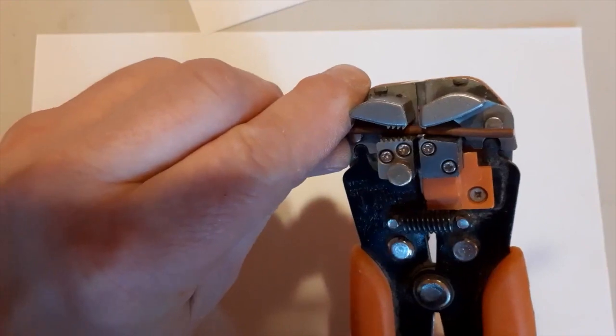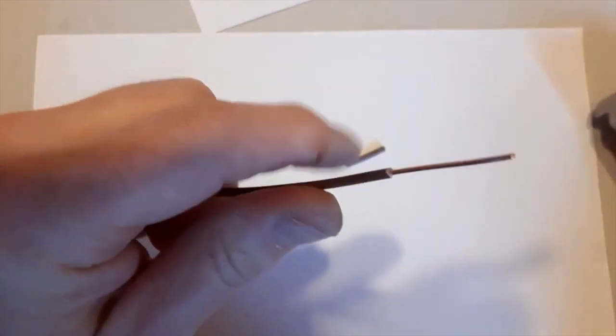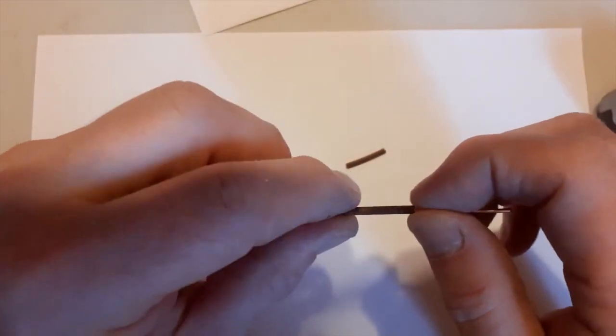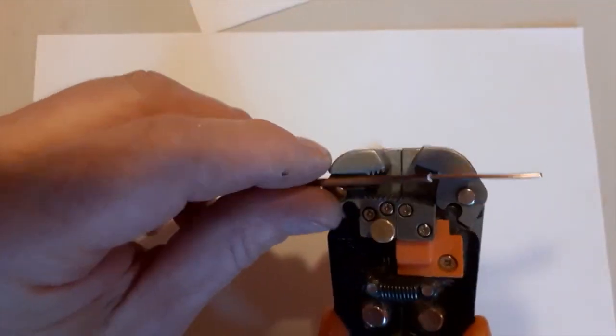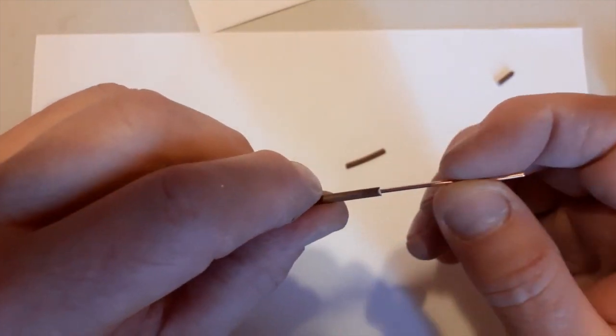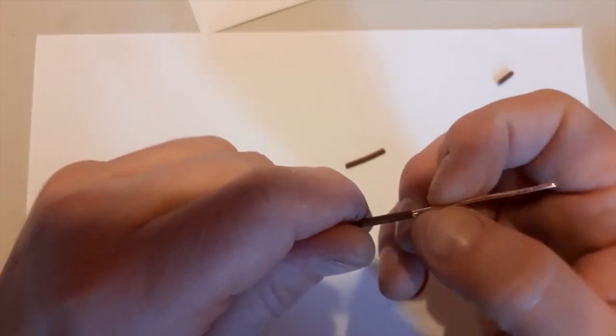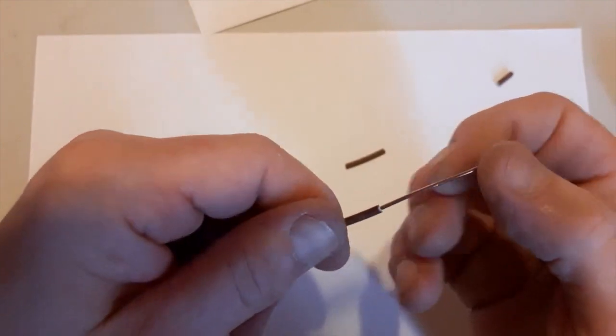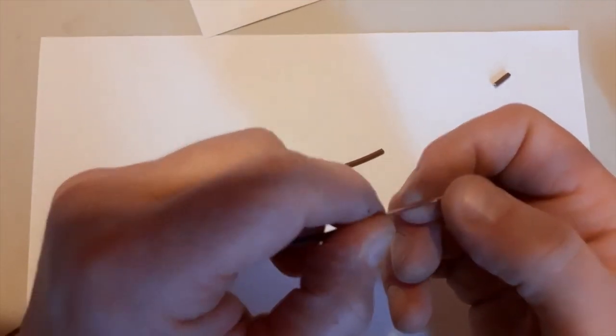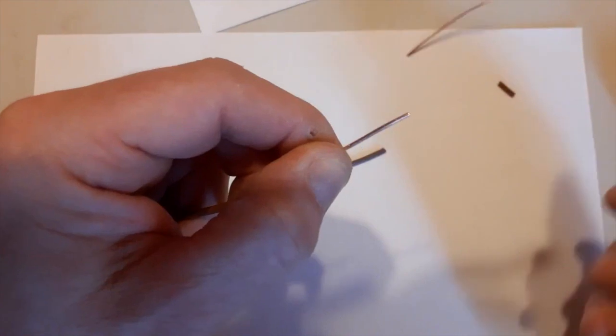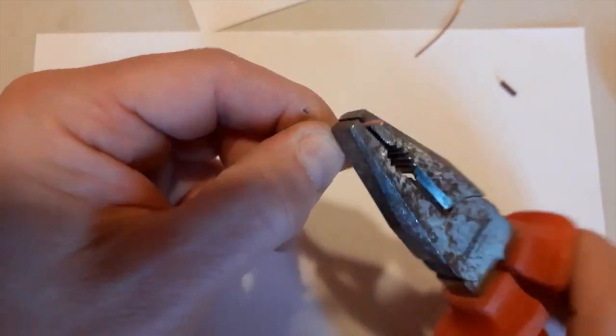Have another go. You're thinking, yeah, but you don't bend the copper conductor like that. It's just in the wall, it's not going to get bent. But what do you think though? You do move the copper conductor around quite a bit when you're actually terminating it. You're moving the socket around a bit, you push it into the socket, move it around, twist it around a little bit, put it back out again possibly. Then somebody might come along in the future, they want to change the socket plate or something.